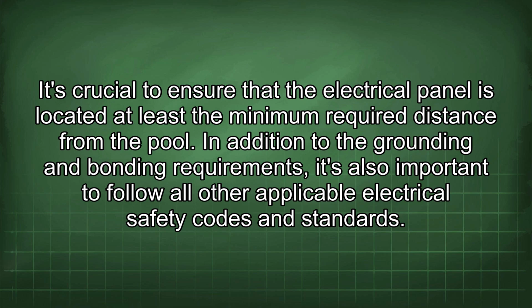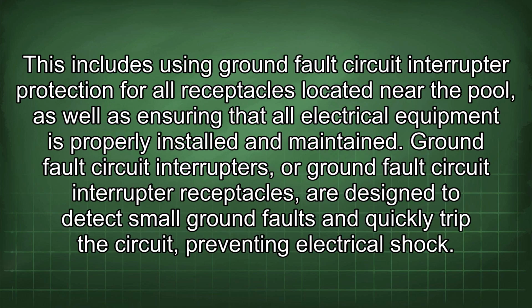In addition to the grounding and bonding requirements, it's also important to follow all other applicable electrical safety codes and standards. This includes using ground fault circuit interrupter protection for all receptacles located near the pool, as well as ensuring that all electrical equipment is properly installed and maintained. Ground fault circuit interrupters, or GFCI receptacles, are designed to detect small ground faults and quickly trip the circuit, preventing electrical shock.